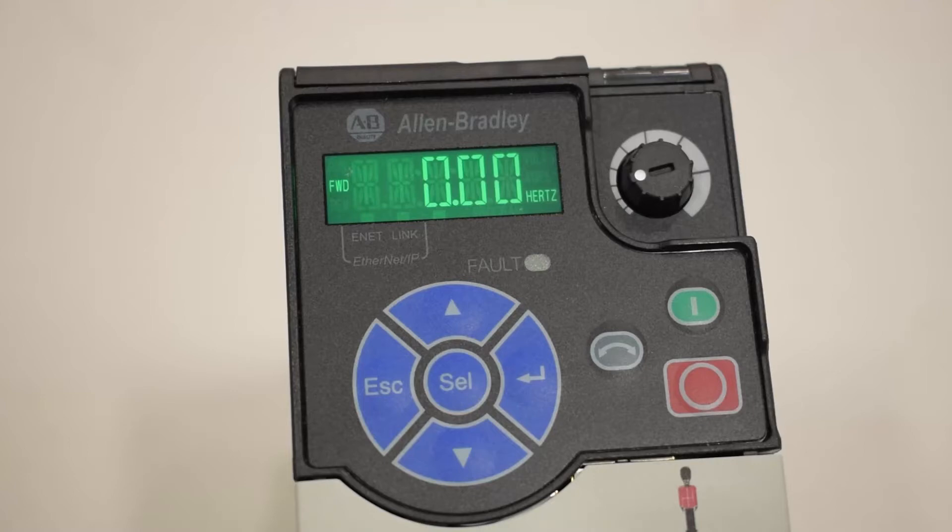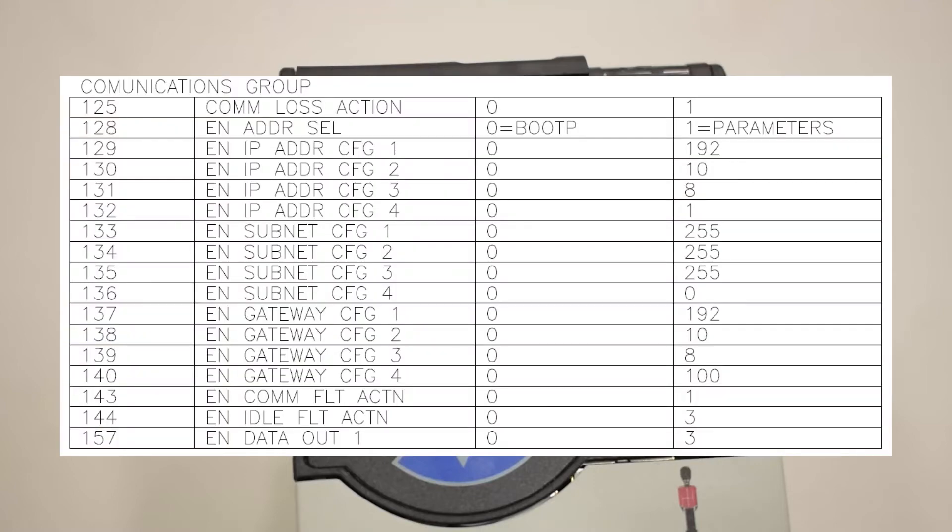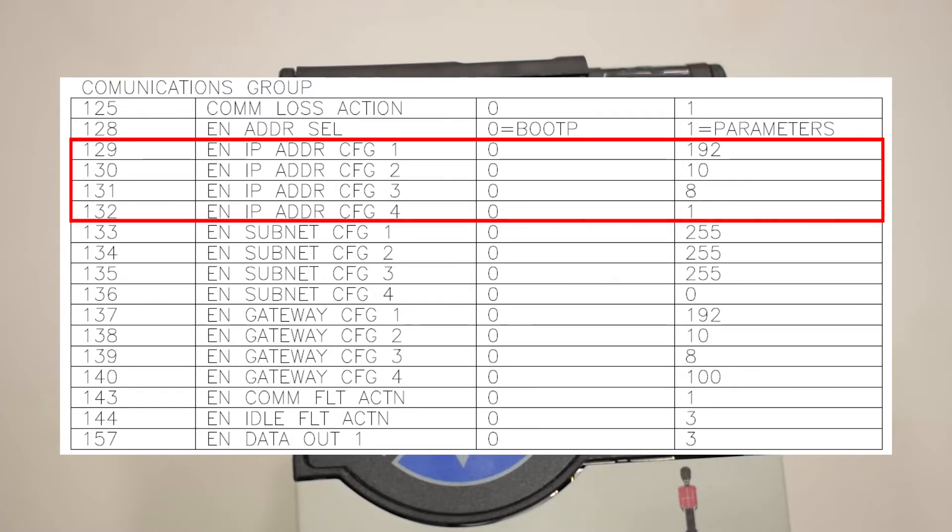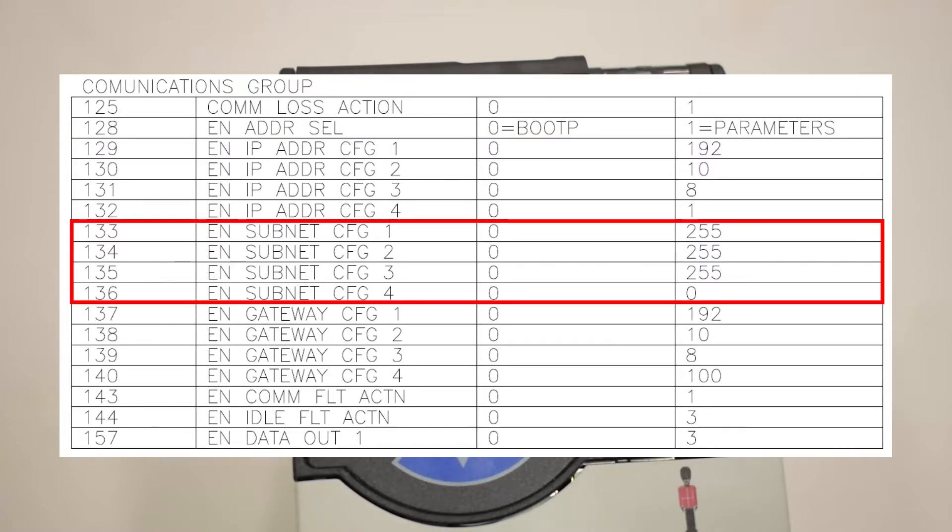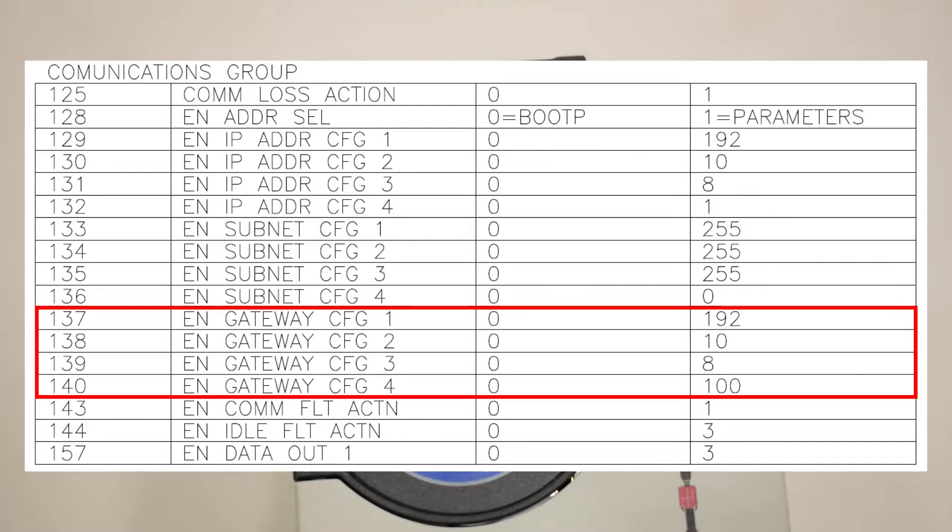Navigate to the VFD parameters table on the element control drawings. Parameters C129 through C132 are used to set the VFD's IP address. Parameters C133 through C136 are used to set the VFD's subnet mask. Parameters C137 through C140 are used to set the VFD's gateway address.